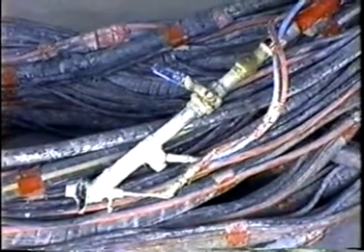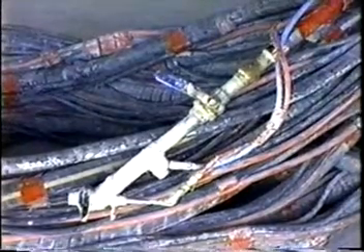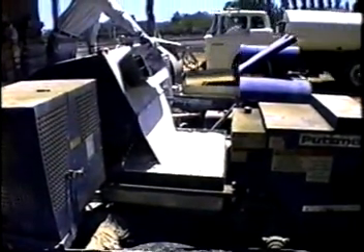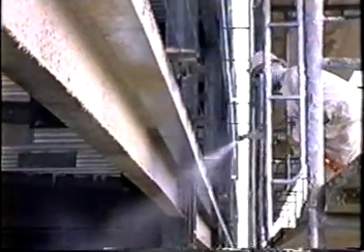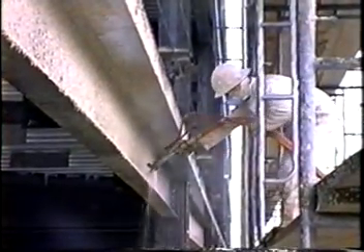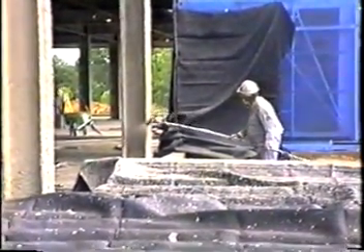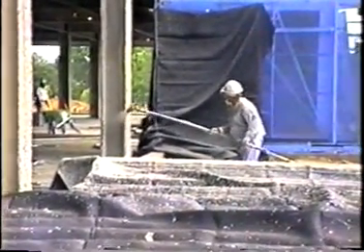For optimum coverage and density, a 5/8 inch inside diameter orifice is recommended. Once all the pumps and hoses have been primed with water at the start of the application, the material is then ready to be discharged from the mixer into the pump hopper. The material valve at the spray nozzle is then opened and the pump switch turned on. When the slurry begins to exit the nozzle, the atomizing air should be adjusted to achieve a uniform spray pattern. It must be made sure that there is no restriction of material.